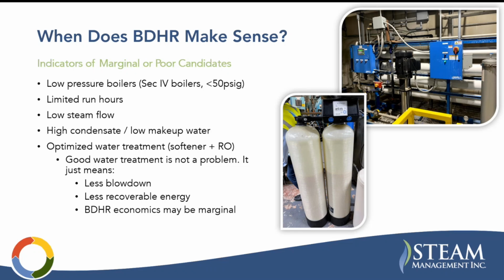A high condensate return or low makeup water, or if they have optimized water treatment, like a softener plus an RO skid. And obviously, good water treatment is not a problem. It just means there's going to be less dissolved solids, which means less blowdown, less recoverable energy, and it's going to make the economics more marginal. Again, these are not hard and fast rules, because you may see an RO skid where the users consume a lot of the steam, and so there's very poor condensate return, or they just have a poor or deteriorated condensate return system. So an RO skid doesn't necessarily mean that it doesn't work, but it's just a clue.